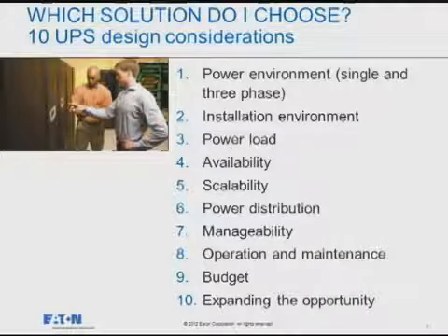Once I have my power requirement, by simply calculating all the loads and adding them, it then tells me whether I'm into single or three-phase. Typically, single-phase applications go up to about 18 kilowatts. Beyond 18 kilowatts, I need to get into a three-phase type of application. So that immediately narrows it down.